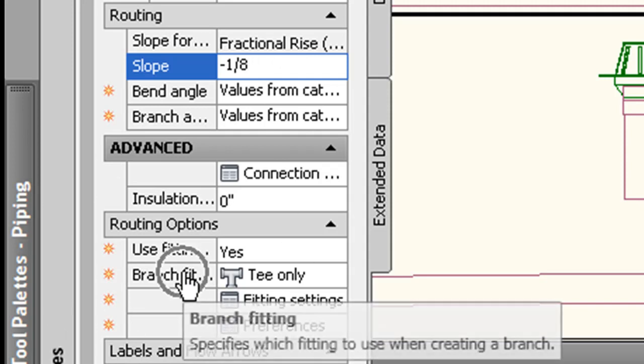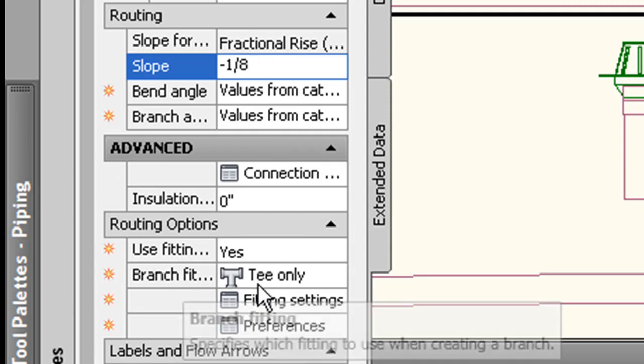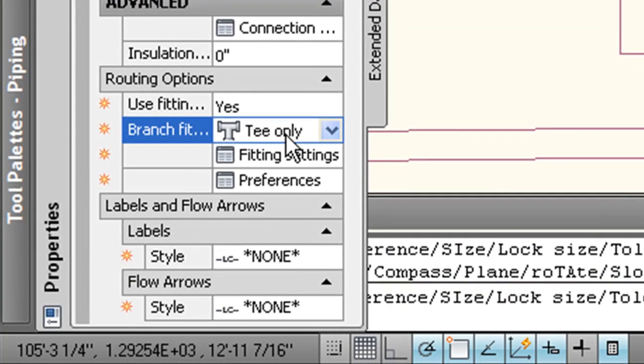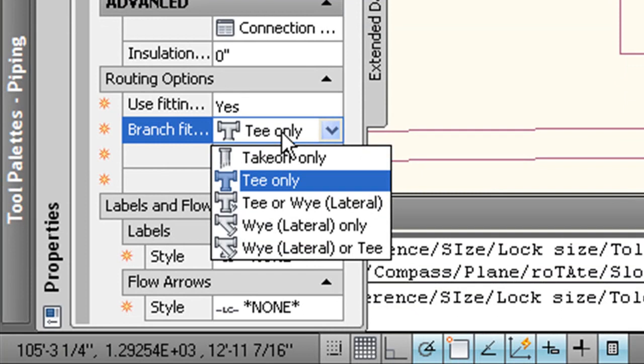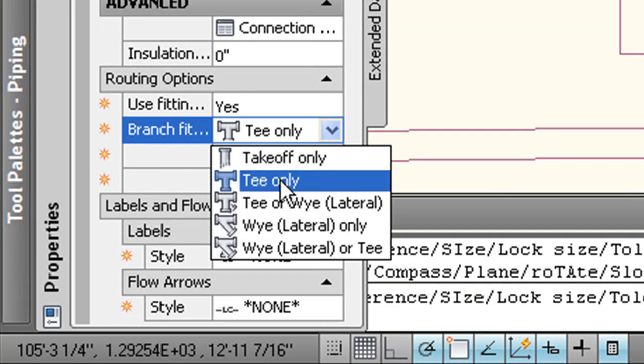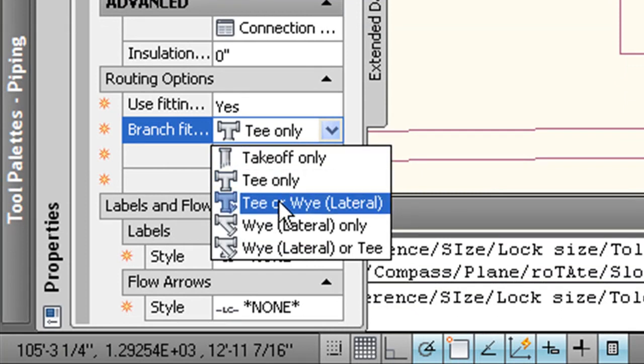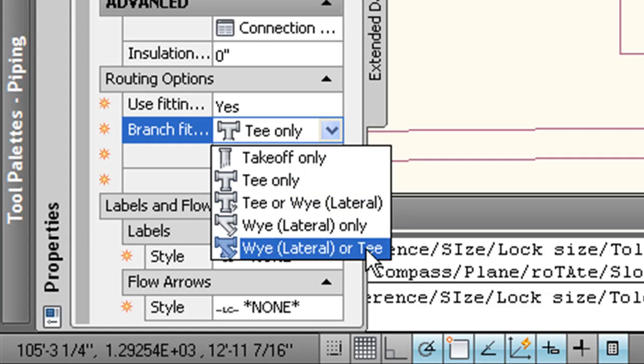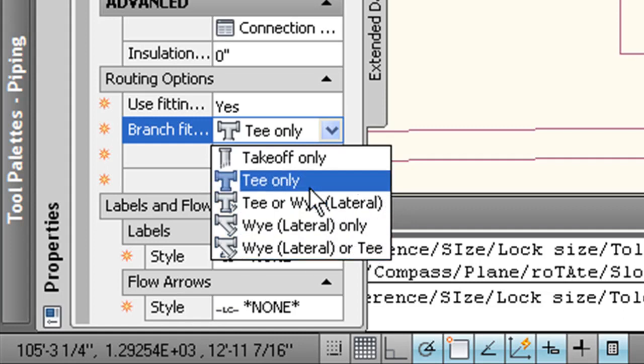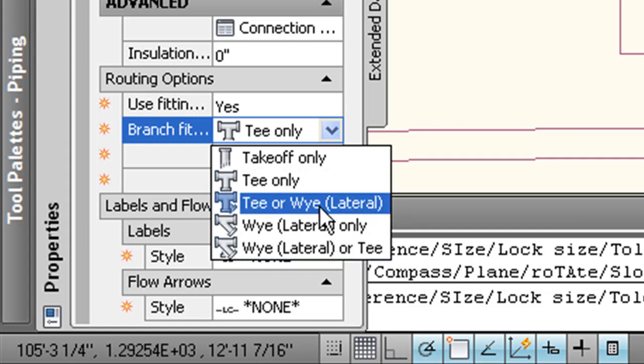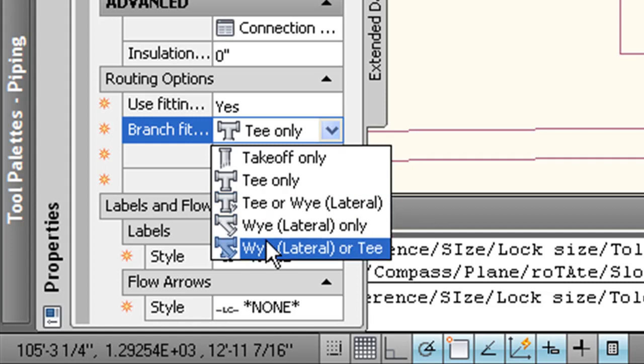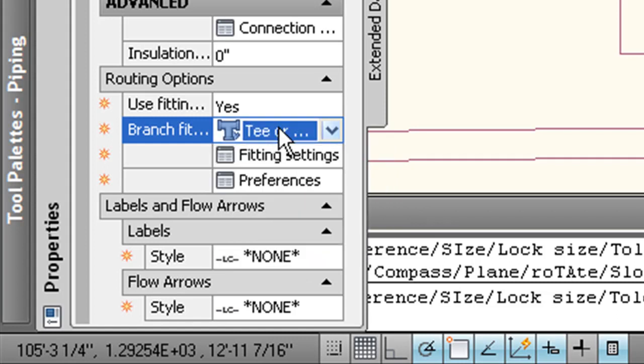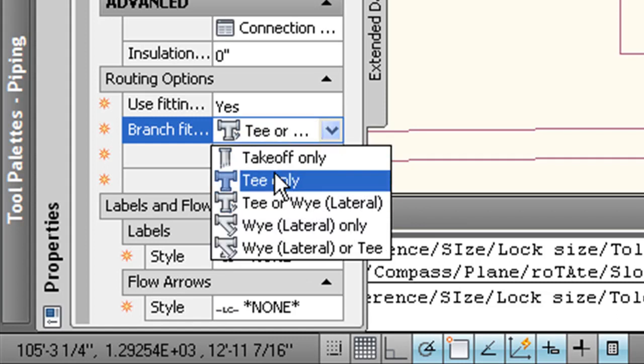And then I'm going to come down here to my branch fittings and check what fitting type I have. Now it's defaulted to T only now. And you can change that to takeoff only, T only, T or Y, Y only, Y or T. Typically, I'll leave it at T or Y only. T or Y means it'll select T first, then Y. This means it'll select Y first, then T. But again, I just leave it at T only or Y only. So in this case, let's leave it at T only.